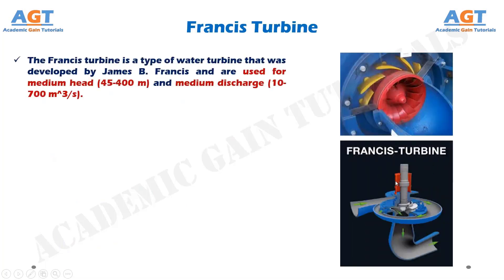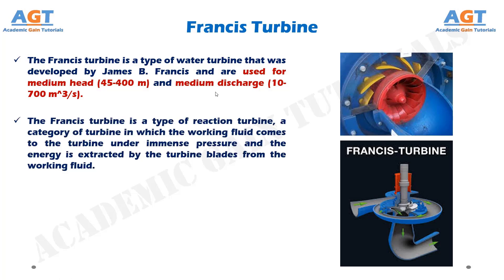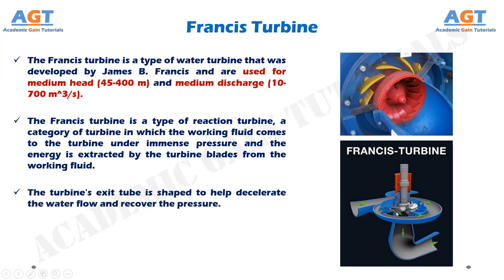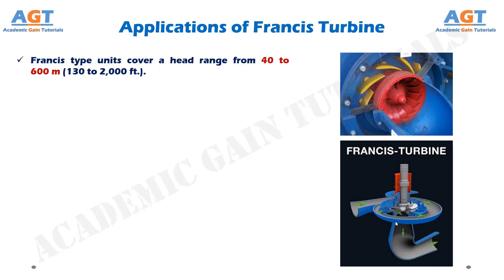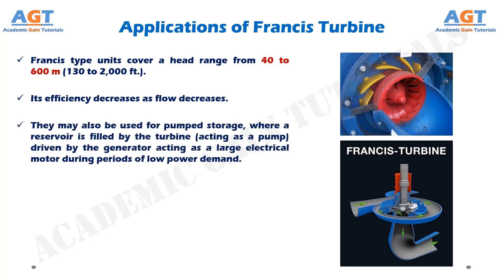The Francis turbine is a type of water turbine that was developed by James B. Francis and is used for medium head and medium discharge, up to 700 cubic meters per second. The Francis turbine is a type of reaction turbine in which the working fluid comes to the turbine under immense pressure and the energy is extracted by the turbine blades from the working fluid. The turbine's exit tube is shaped to help decelerate the water flow and recover the pressure. Water flow is radial from exterior to interior. Francis type units cover a head range from 40 to 600 meters. Its efficiency decreases as flow decreases. They may also be used for pump storage, where a reservoir is filled by the turbine acting as a pump, driven by the generator acting as a large electrical motor during periods of low power demand.